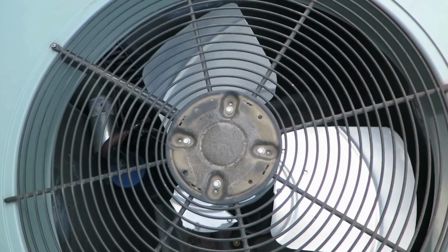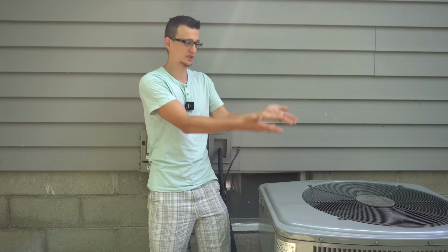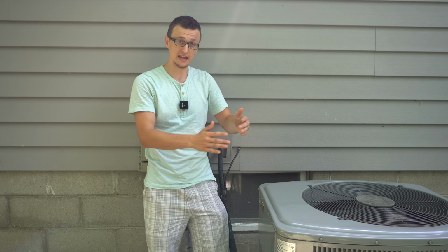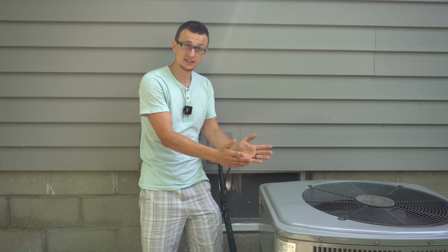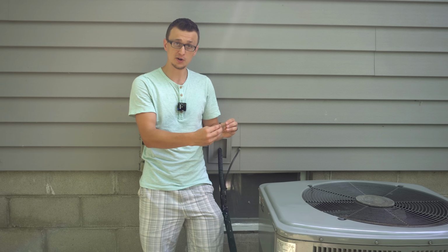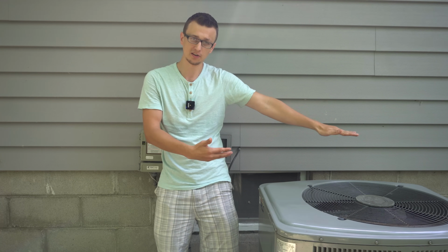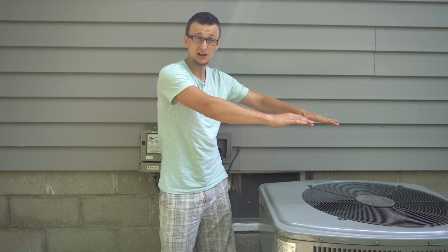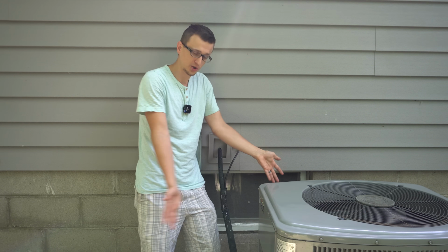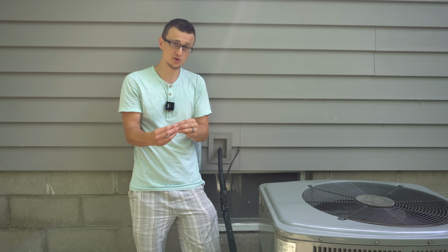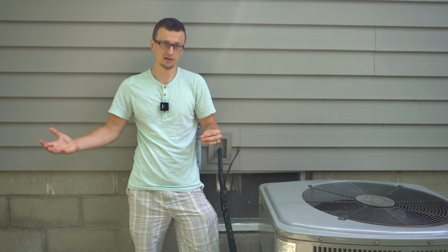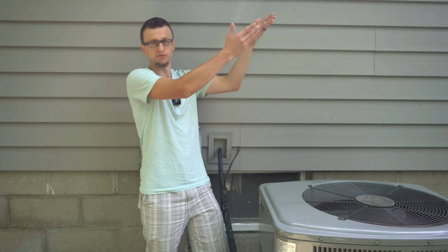Next, the fan that is on top of the unit, when it's running, it sucks air from the sides and then pushes it out through the top. As it's doing that, the air that goes by the coils is actually cooler than the refrigerant inside the pipes, so the refrigerant ends up cooling off, or giving up some of its heat into the air. That's why oftentimes when you put your hand on top of a running air conditioner, the air coming out on top is hot. That's because as it goes through the coils, it absorbs the heat in the refrigerant, because the refrigerant is hotter than the air outside, and then it rejects it from the top.